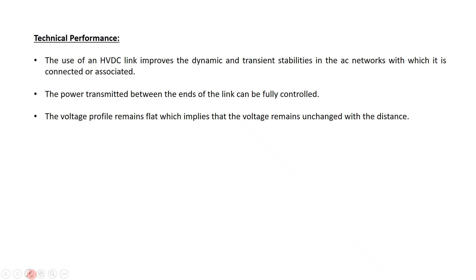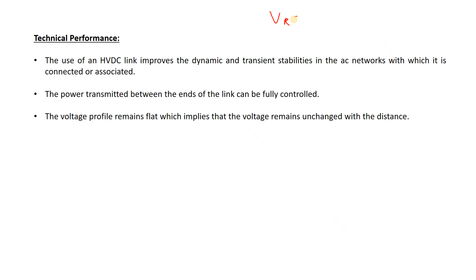Okay, and one more important thing, in DC there is no reactance. Because in AC, the receiving end voltage is equal to the sending end voltage minus I into Z. And what is Z? Z is equal to R plus jXL. And there is capacitance also, because you have studied the performance of transmission lines, isn't it? ABCD parameters, voltage stability, long transmission, short transmission, medium transmission. But DC is generally used in long transmission and it has only resistance. So the receiving end voltage is only equal to the sending end voltage minus I into R.